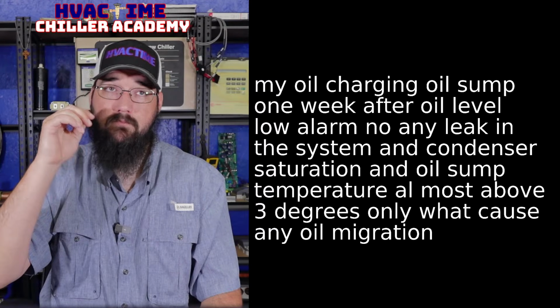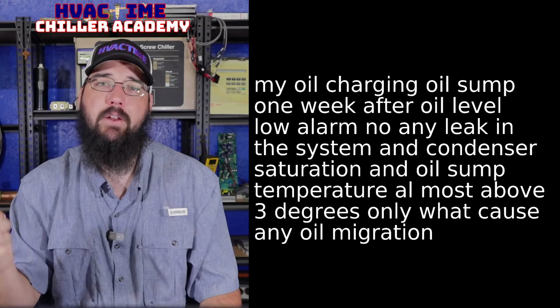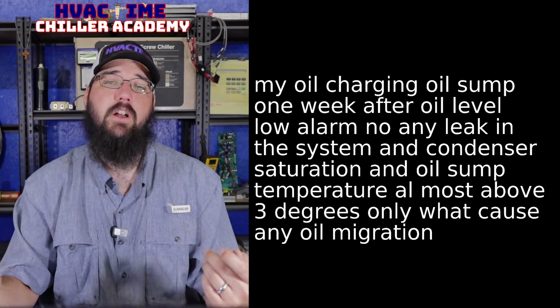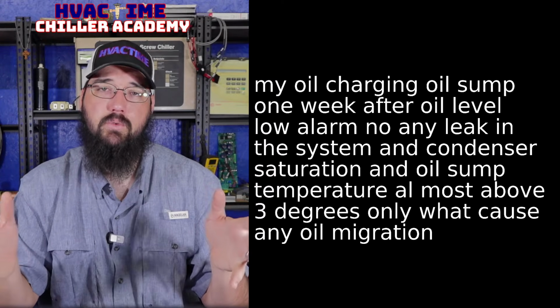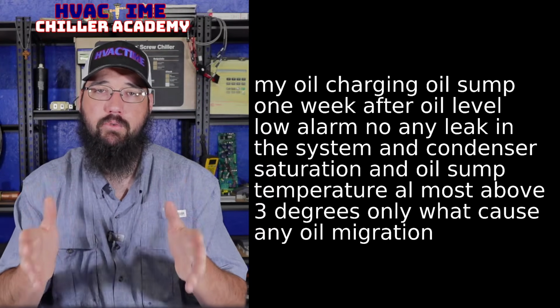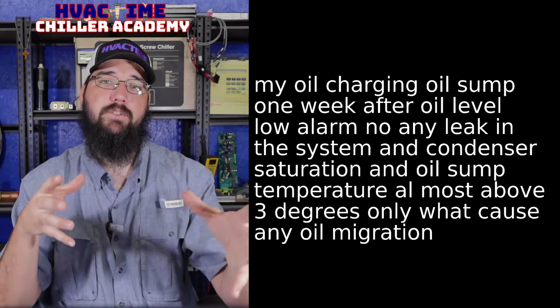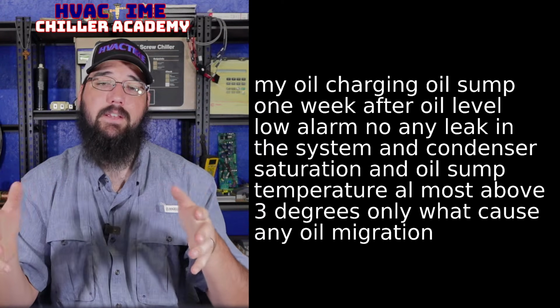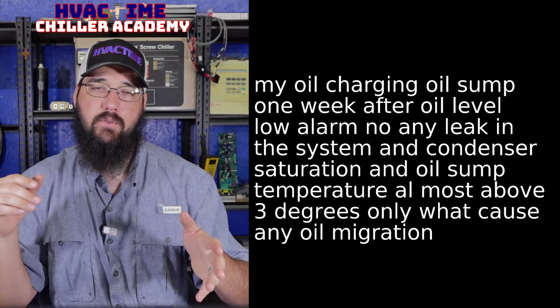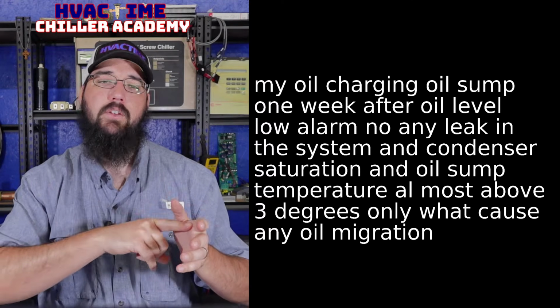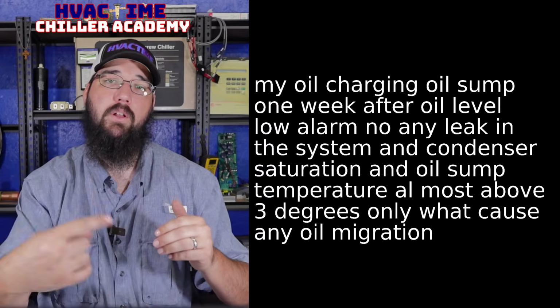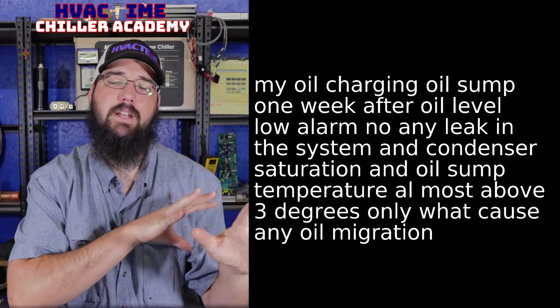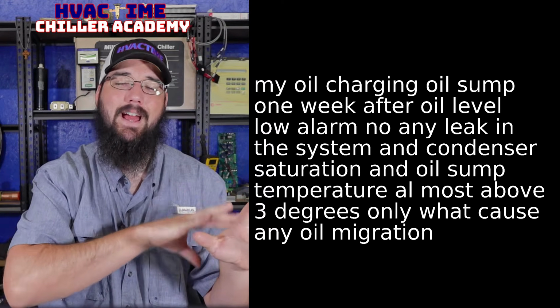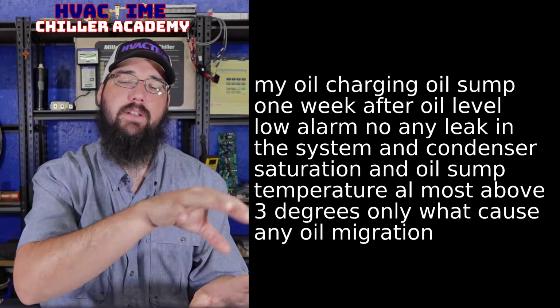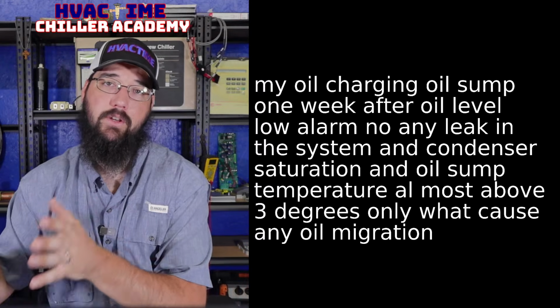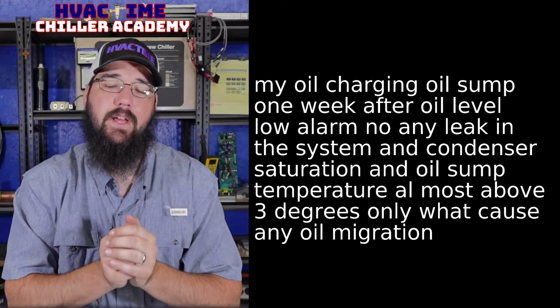Now that can be tricky. If you're trying to bring on a machine that migrated in the off cycle, which is very common, especially because a lot of these circuits share an evaporator with another circuit. So that evaporator may be a 2-circuit or 3-circuit evaporator, with multiple refrigerant circuits acting on it. It may be the case that Circuit 2 hadn't run for quite some time. Circuit 1's been online maintaining the load. Circuit 2 finally goes to come on, but all of the oil has already migrated because the manufacturer did not have isolation on the oil circuit to prevent migration when the other circuit is online. But that other circuit's creating a cold evaporator and making it easy for that oil to migrate.